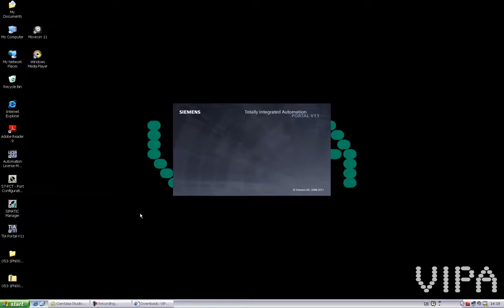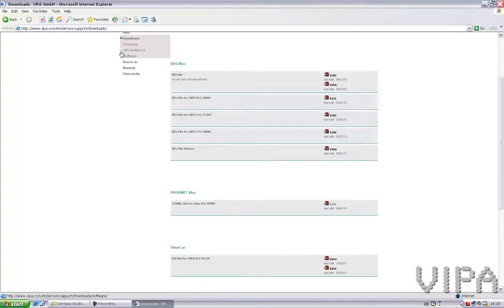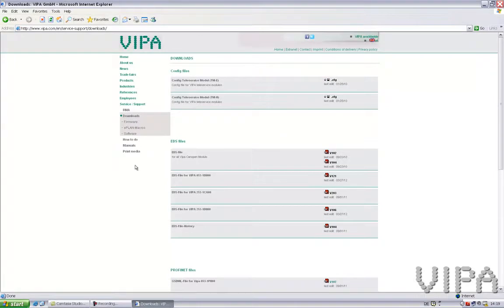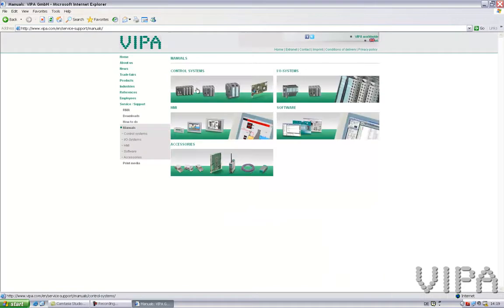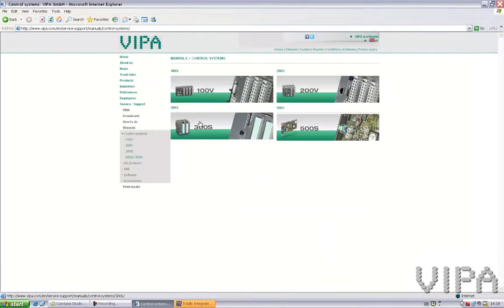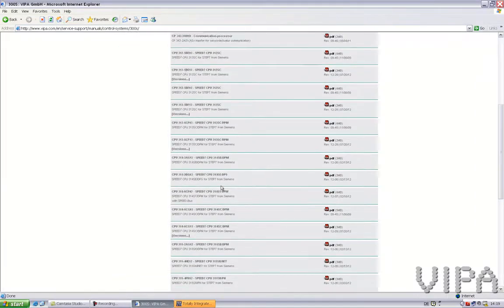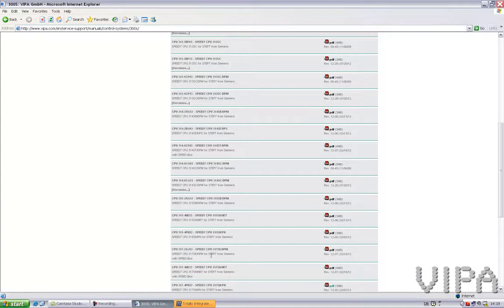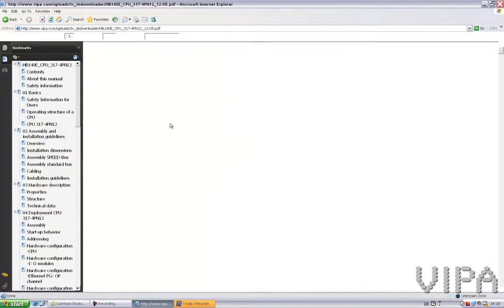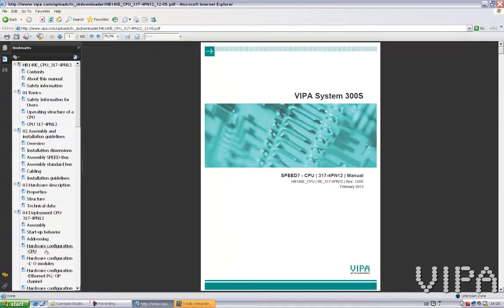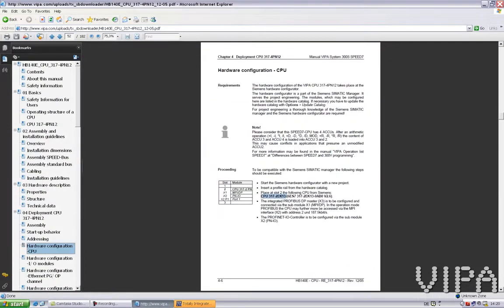In TIA Portal I will have to create a small project to make this configuration. For creating this project I will need to know what CPU type I need to select. While Siemens is starting TIA Portal I will go to the Vipa Speed home page and select the right manual to see what CPU I need to configure. I go to Control System, 300S, and I will find 317PN from Vipa — it's this one. And in the hardware configuration I can see that it's exactly this one we need to select.